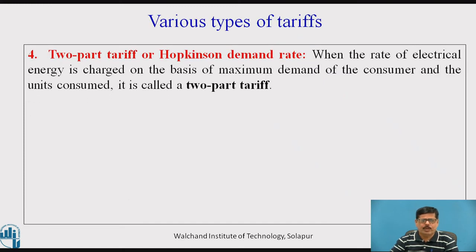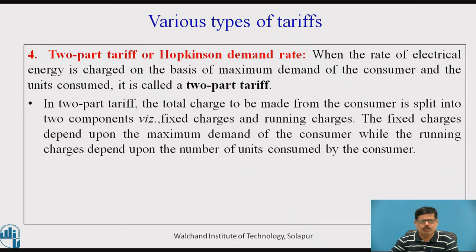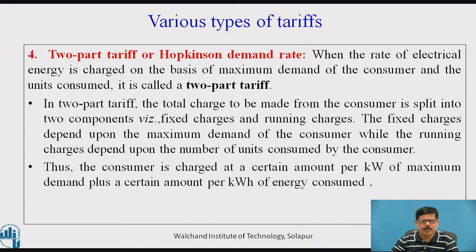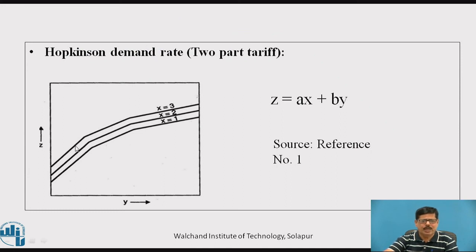The next form is the two-part tariff or Hopkinson demand rate. When electrical energy is charged on the basis of maximum demand plus number of units consumed, it is called a two-part tariff. The total charge is split into two components: fixed charges (depending on maximum demand) and running charges (depending on units consumed). The consumer is charged at a certain rate per kilowatt of maximum demand plus a certain amount per kilowatt-hour of energy consumed: Z = AX + BY.